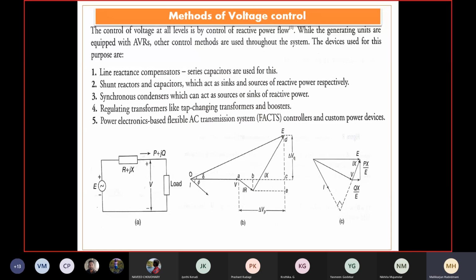Being inductive by nature, the reactance causes an additional burden on the system. So the reactance of the line needs to be compensated. We cannot make it zero because a transmission line possesses a specific inductance and reactance per kilometer of length. Then how do you compensate that? You need to reduce its offered reactance over the length by additional compensation mechanisms.